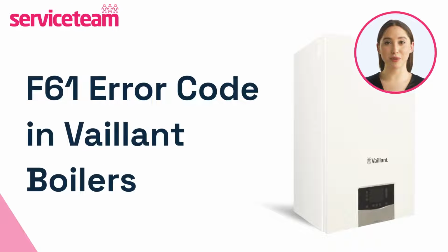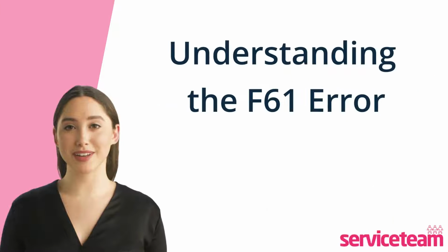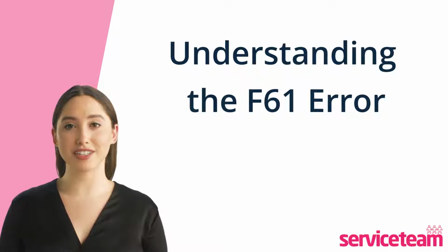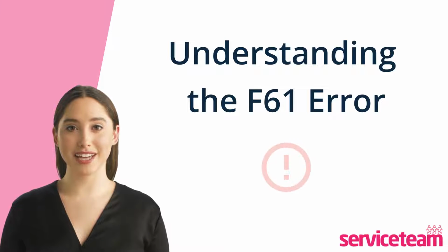If you have a Vaillant boiler, you might have experienced the F61 fault. Here, we are going to find out how to fix the F61 error code in Vaillant boilers. The Vaillant F61 fault code usually appears when a component fails or when the wiring between the PCB and the gas valve is faulty.